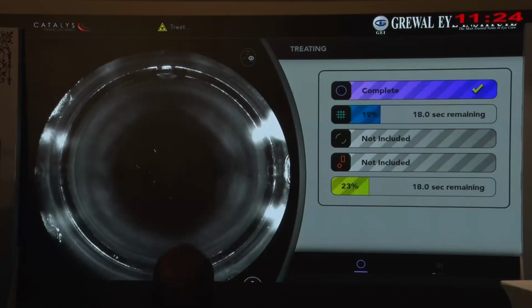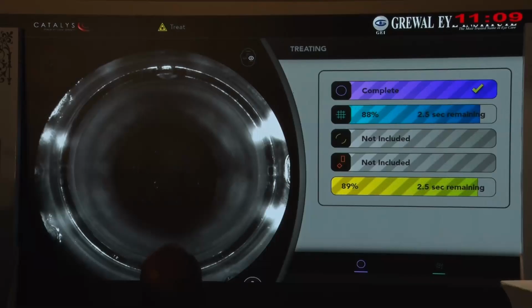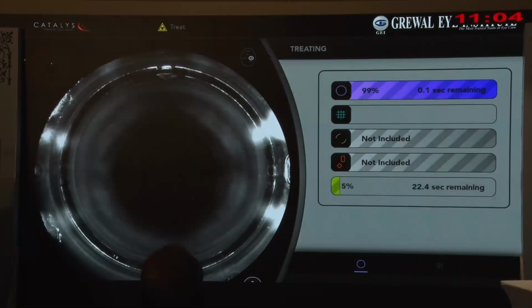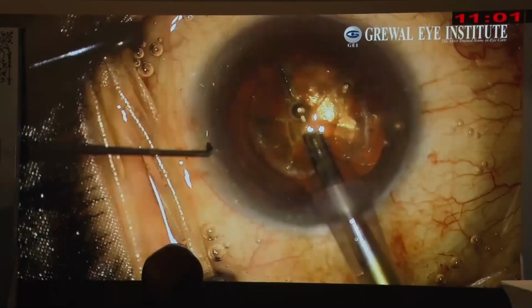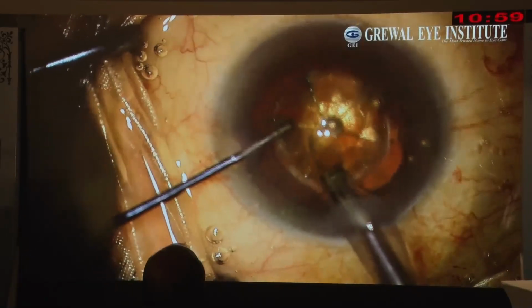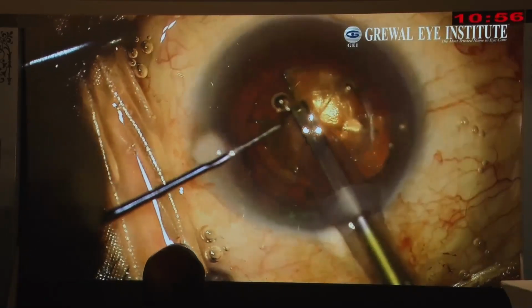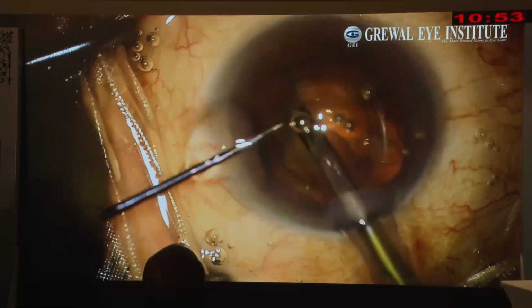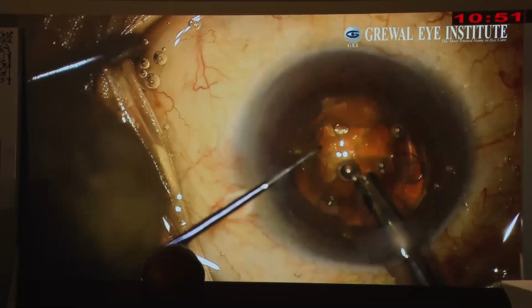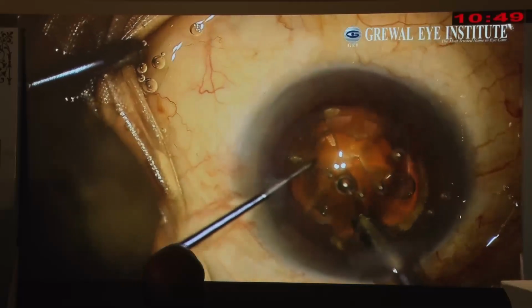So what differences are required in doing the settings of the FLACS? One is you reduce the spacing of the spot, you increase the energy, and normally we keep it at 3 passes, but for hard cataract I'll be putting it at 5 passes. So you need to change the settings of the FLACS machine for a hard cataract so that you are able to cut through the hard lens. So you have a good capsulotomy in all cases of hard cataract with FLACS, which to my mind is a huge advantage.